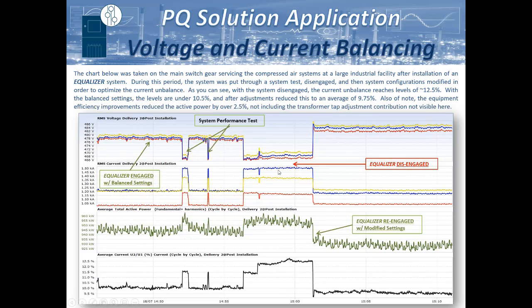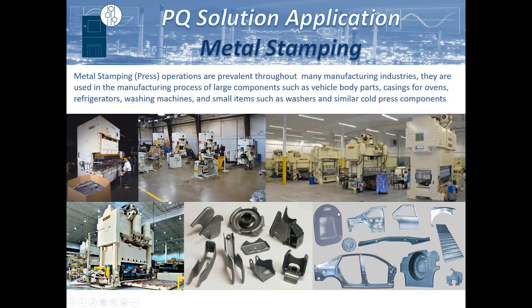What that ended up doing is, you can see that when the system is disengaged, there's a fairly significant amount of current imbalance, which is not unheard of these days, depending on the types of equipment and the processes in place. Once we tweak the settings a little bit, we raise the voltage even higher, just by a little, but we better balance the current loads. In doing so, you can see a marked improvement in the active power from disengaged to engaged. Then by tweaking some of the settings, we could get that down a little bit further.